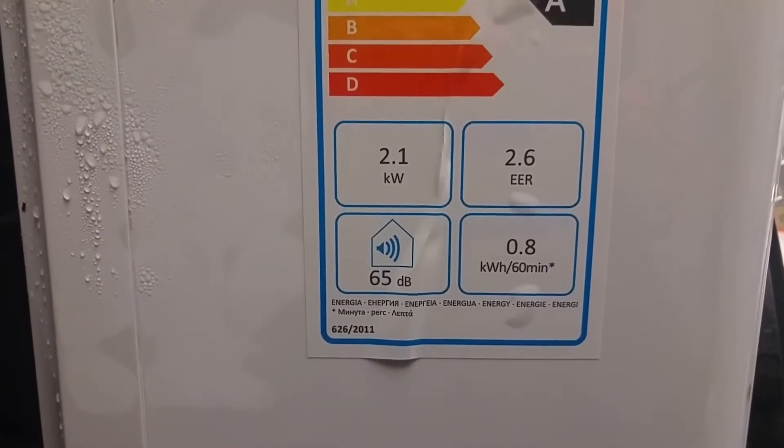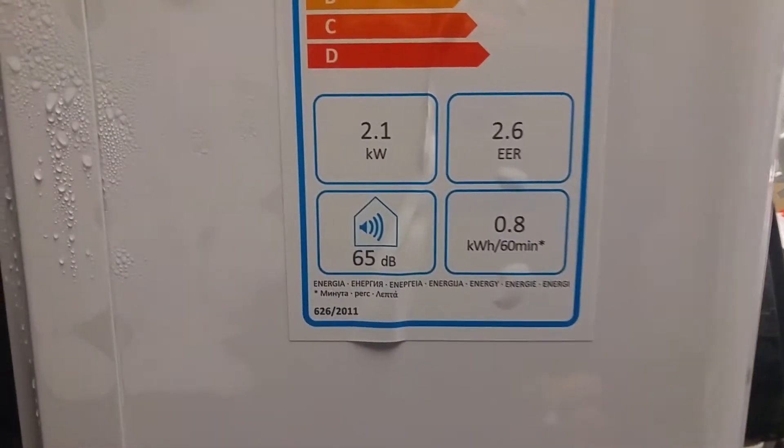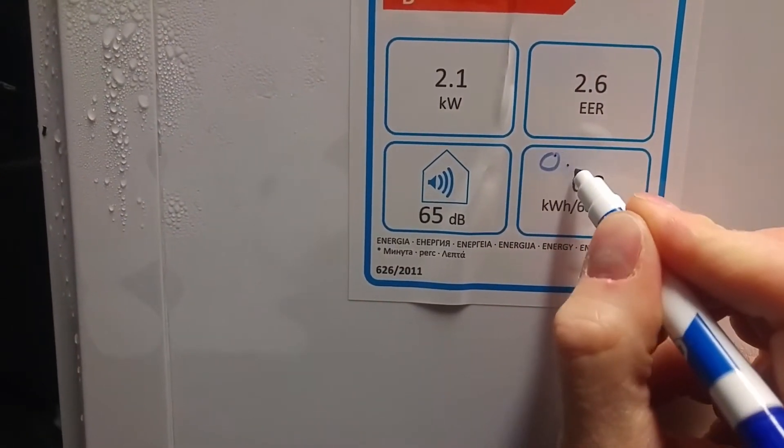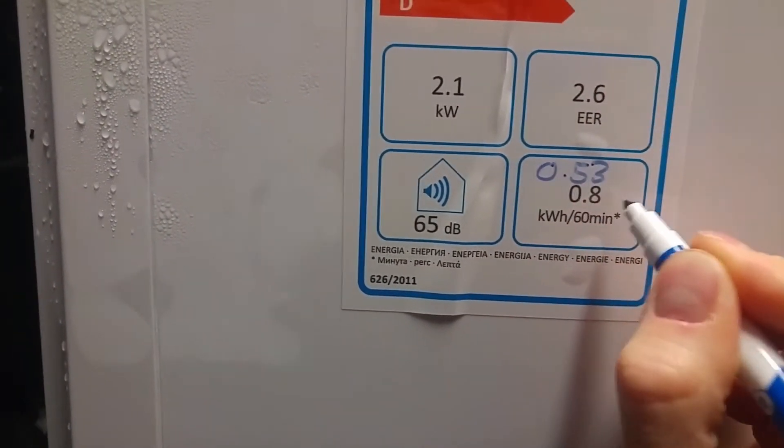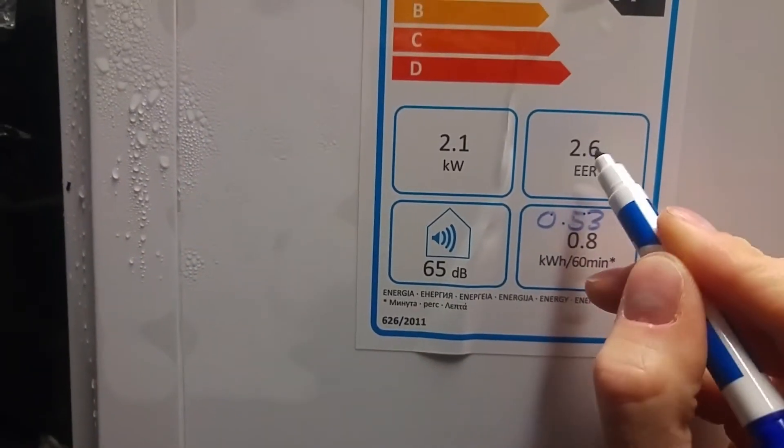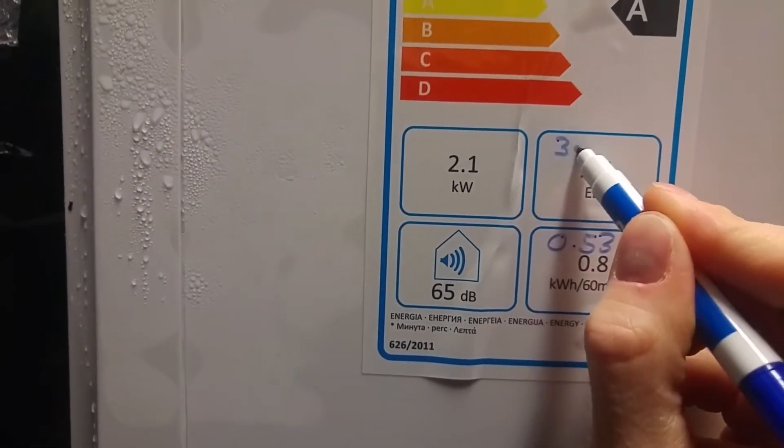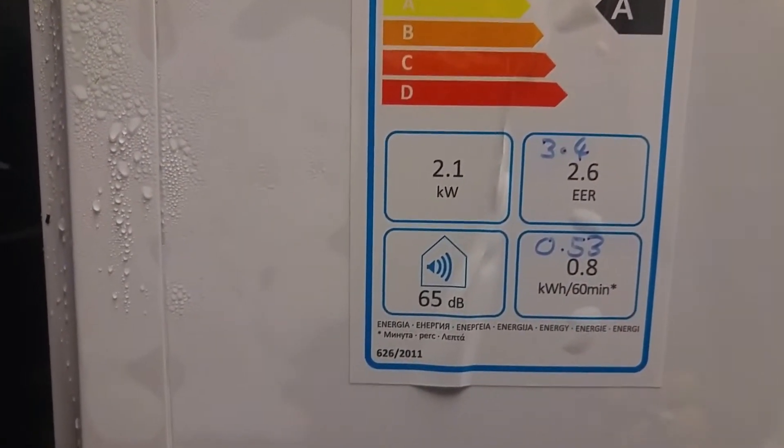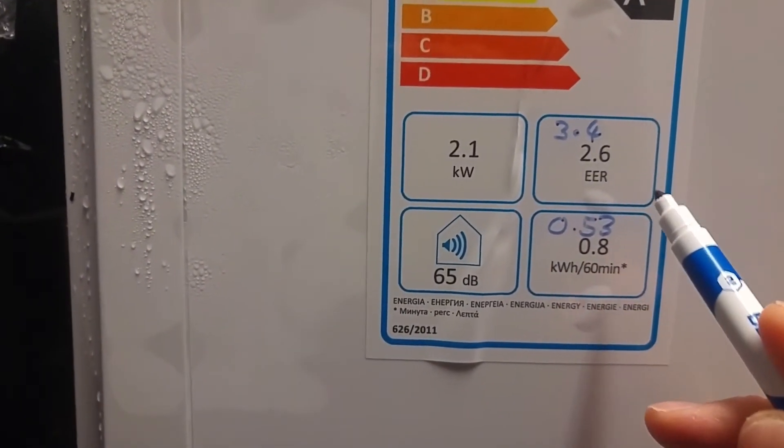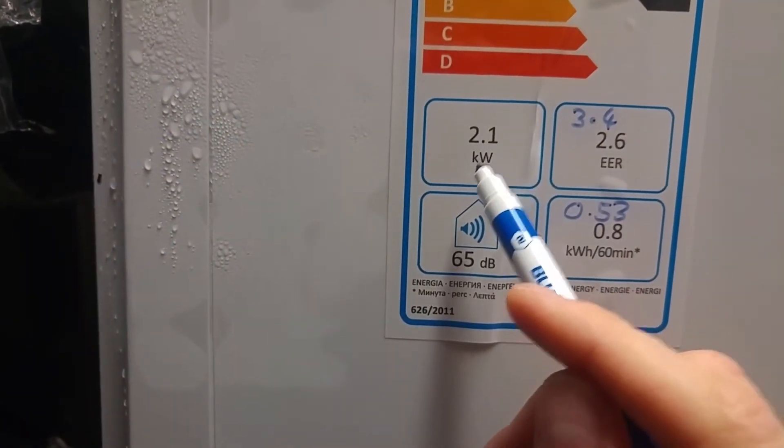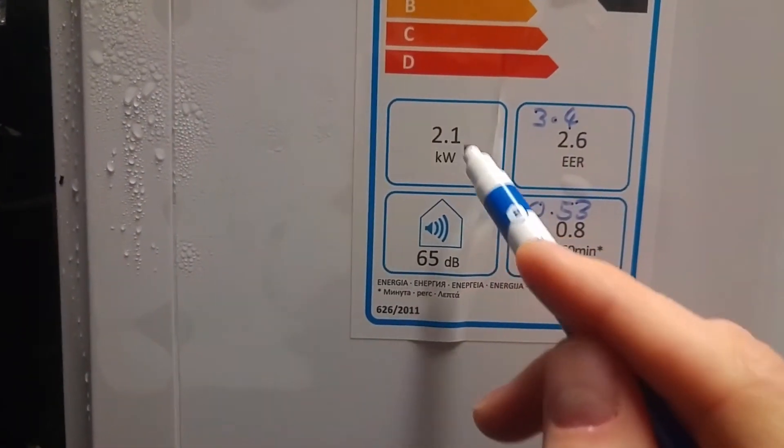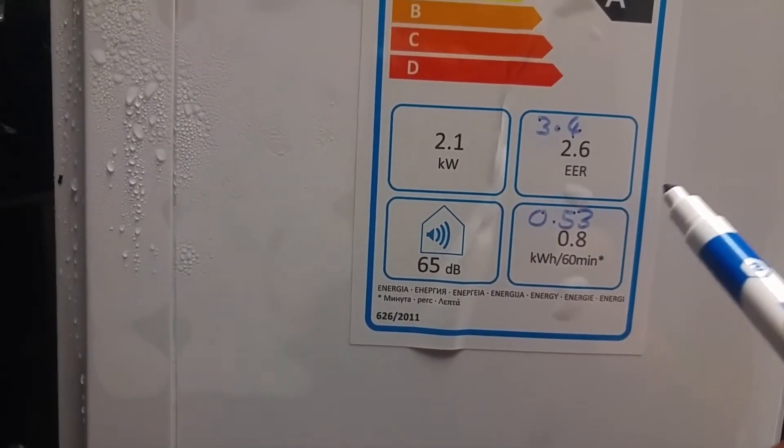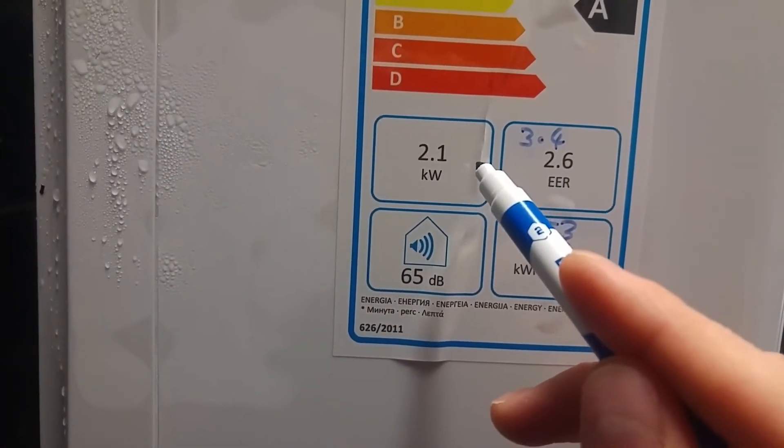Interesting to compare our results to the manufacturer's specifications. Because we got 0.53 for the power draw and we got 3.4 for the coefficient of performance. And that's better than what they've said. But the power output we got less because they just multiply these two together.